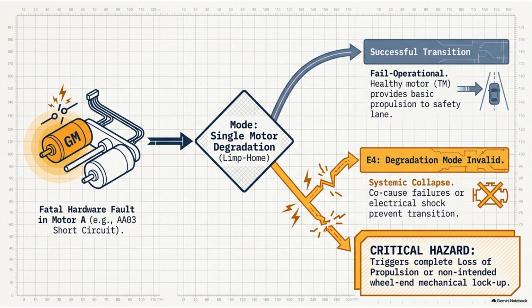To put that in perspective, a standard house circuit breaker trips at, what, 15 or 20 amps? Right, 20 amps and your lights go out. And we are talking about 5,000 in a microsecond. It is an incomprehensible amount of instantaneous energy. And when that 5,000 amp spike hits the high voltage side, it induces a severe reaction on the low voltage side, even with heavy filtering in place. It bleeds over. It does.